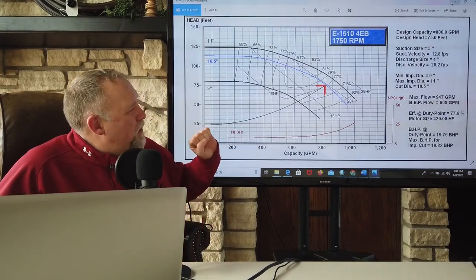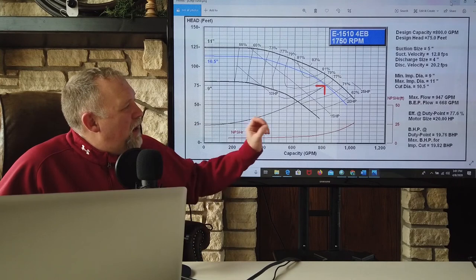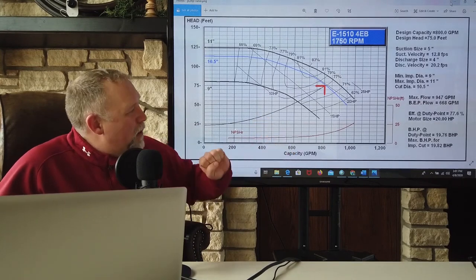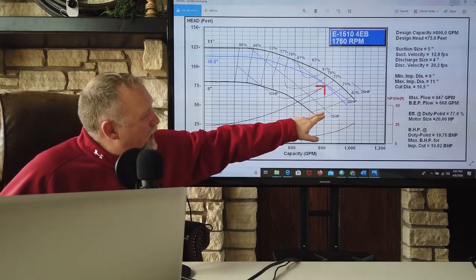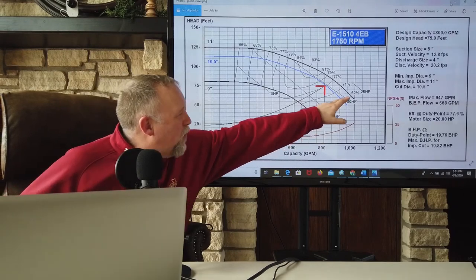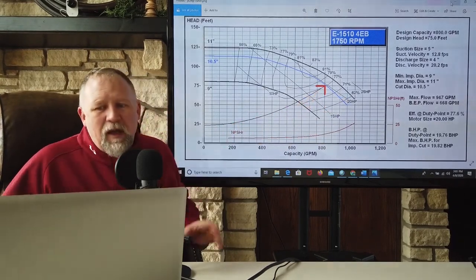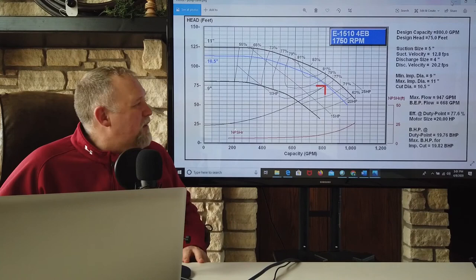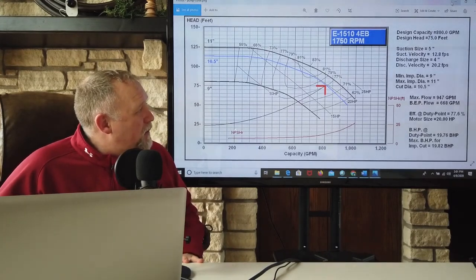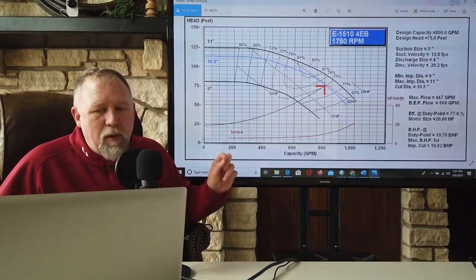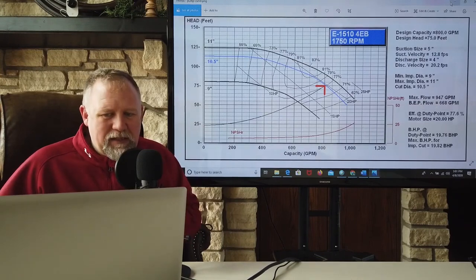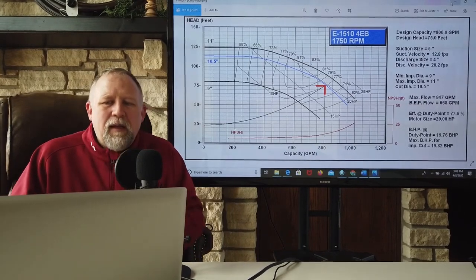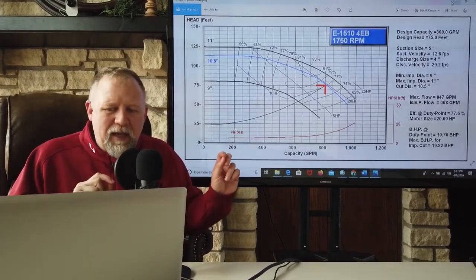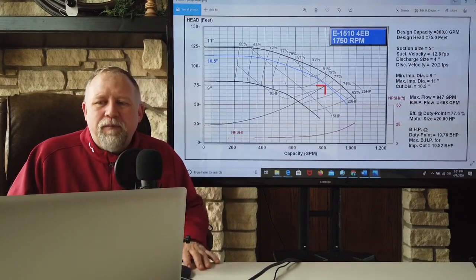I would also expect you to be able to give me an approximation of the operating pump power. In other words, if I'm between the 15 horsepower curve and the 20 horsepower curve, I'd expect you to be able to roughly approximate it. And I would also expect you to be able to pick which motor would be the best choice for operating based on the guidelines that I've given you.